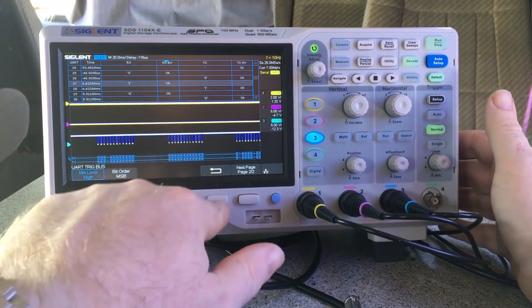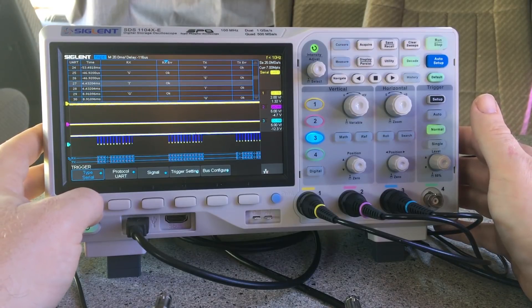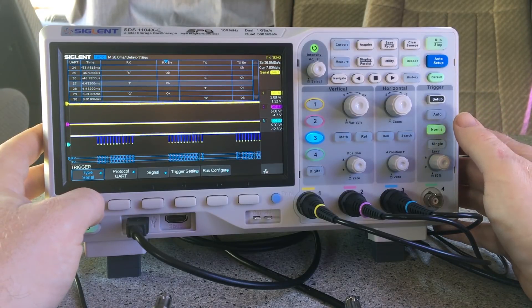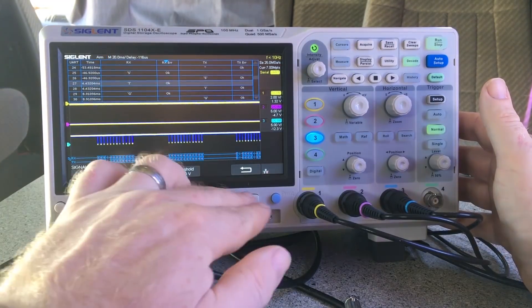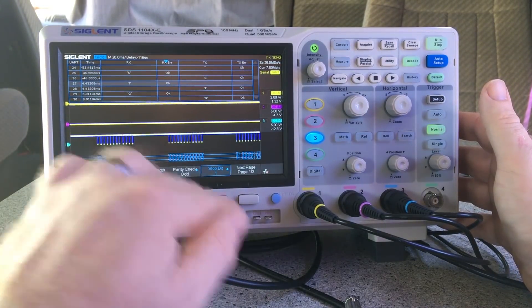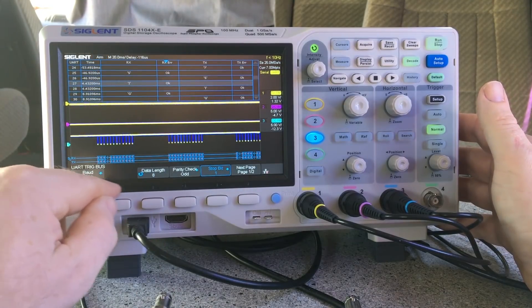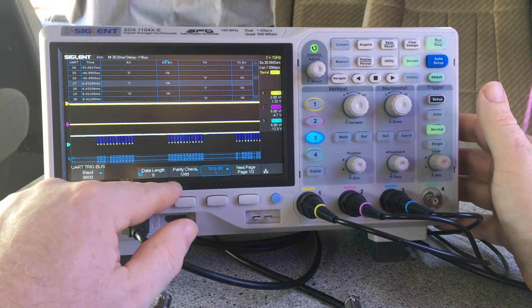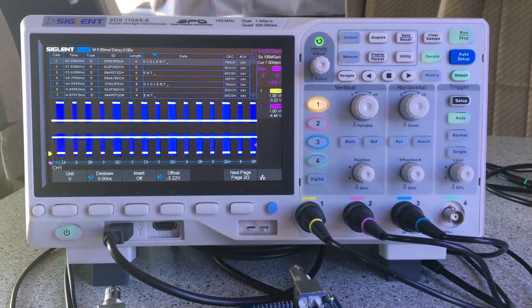The trigger is also tied into it, so if you change things in one place it changes in the other — they're linked together, it's not obvious but they are. It makes things easier for trigger settings. The bus configuration on this board is 9600 baud, with the data length and so on set accordingly.